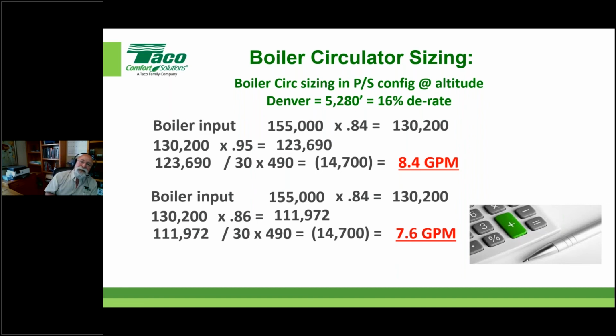And here's the kicker: most of you folks have a real easy way of telling how big the boiler circulator is, and folks, the boiler manufacturer nowadays, remember I said, they always are looking at the supply and the return of the boiler's heat exchanger. They're showing you what the delta T is. And folks, if it's not out there where it should be, turn the damn pump down. And if you're already on low and you're still at 10 and 5-degree delta Ts, you might want to think about putting a pump that's more appropriately sized in there.